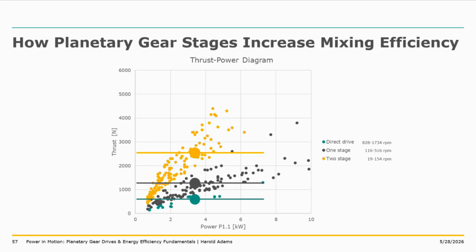And then third, we've got the planetary gear system. So the two-stage planetary gear system. And what exactly does it mean? So if we use, for example, a motor input with 3.5 kW for a direct drive mixer, we average approximately 500 to 800 newtons of thrust, respectively.